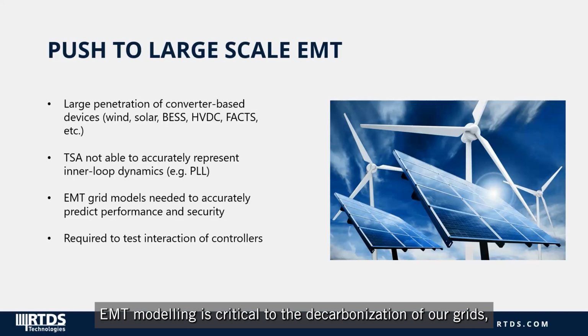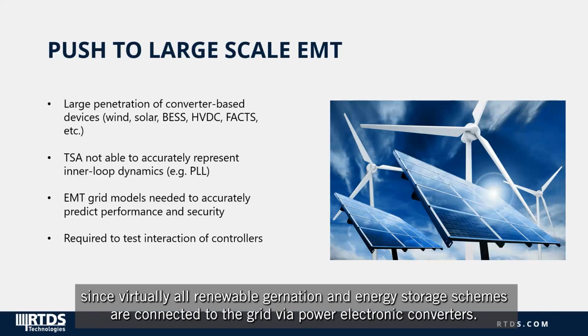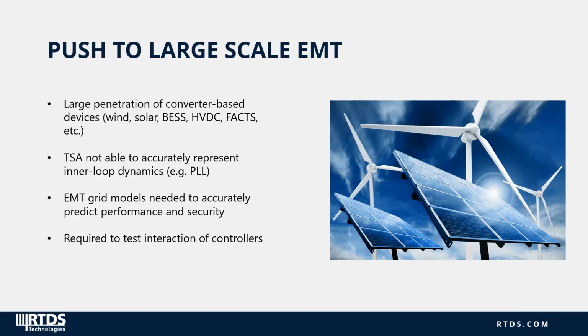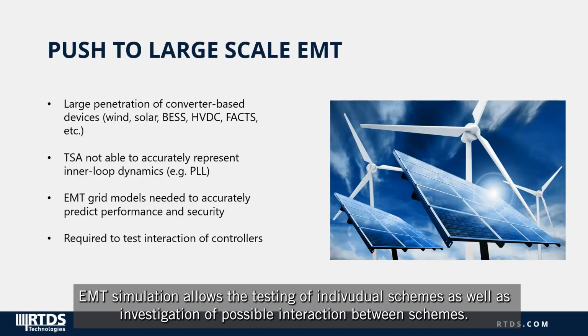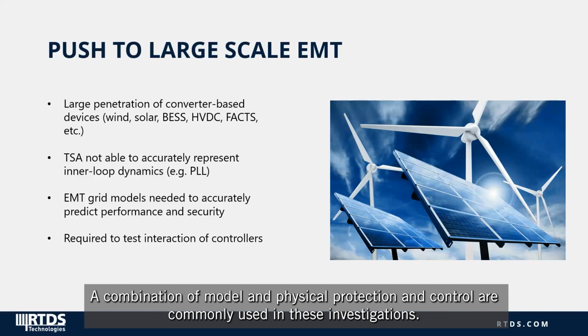EMT modeling is critical to the decarbonization of our grids, since virtually all renewable generation and energy storage schemes are connected to the grid via power electronic converters. EMT simulation allows the testing of individual schemes as well as investigation of possible interaction between schemes. A combination of modeled and physical protection and control are commonly used in these investigations.